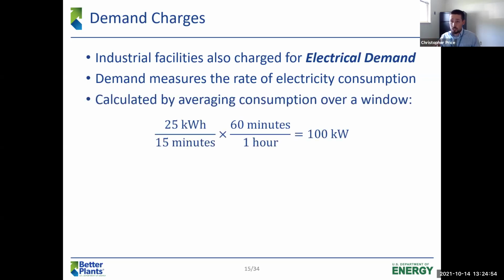So the way your utility calculates demand is there'll be a separate meter that calculates your average energy consumption over a given window. Normally that's 15 minutes, although it can be 20 or 30 minutes - it depends on what kind of metering your utility does. For example, you could watch your consumption meter, time it over a 15-minute window. If it goes up by 25 kilowatt hours in 15 minutes, divide the kilowatt hours by minutes, change minutes to hours. 25 kilowatt hours in 15 minutes is 100 kilowatts of demand.